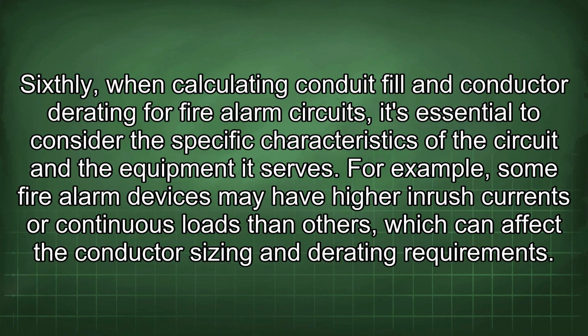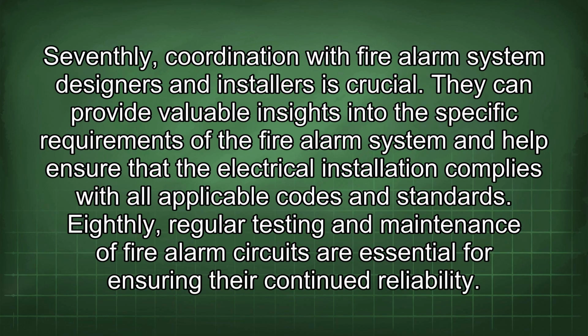For example, some fire alarm devices may have higher inrush currents or continuous loads than others, which can affect the conductor sizing and derating requirements. Seventhly, coordination with fire alarm system designers and installers is crucial. They can provide valuable insights into the specific requirements of the fire alarm system and help ensure that the electrical installation complies with all applicable codes and standards.